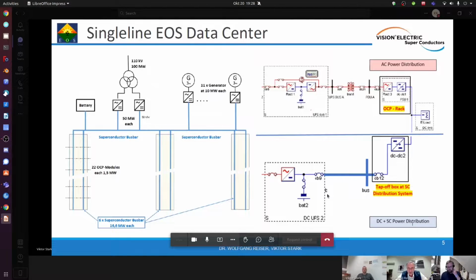So this does not give additional problems. I've spoken to data center operators who tell me that year by year they experience failures of power supplies in the racks, and they have to exchange between 5 and 10% of the power supplies simply because they are not working correctly due to unbalanced potentials between A and B power supplies. That is possible, not in all data centers, but sometimes it happens. Yeah, that is definitely an issue.